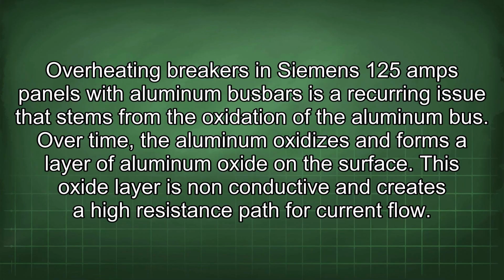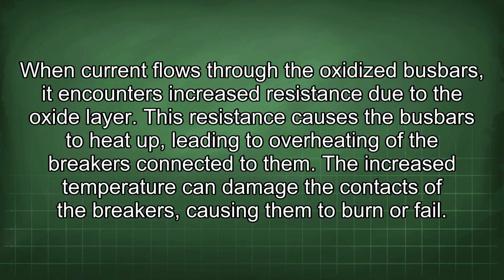Overheating breakers in Siemens 125 amp panels with aluminum busbars is a recurring issue that stems from the oxidation of the aluminum bus. Over time, the aluminum oxidizes and forms a layer of aluminum oxide on the surface. This oxide layer is non-conductive and creates a high resistance path for current flow. When current flows through the oxidized busbars, it encounters increased resistance due to the oxide layer. This resistance causes the busbars to heat up, leading to overheating of the breakers connected to them.